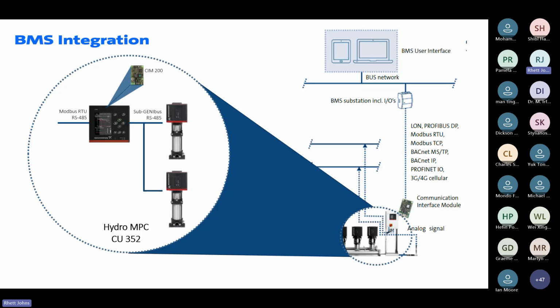Implementing a distributed control strategy in your pump will allow you to have full transparency of the energy consumption and performance of your systems. What I mean by distributed control strategy is that you have localized control within those systems, such as a pump skid, and that pump skid then knows the energy consumption of each individual component within it. So using communication standards such as Profinet, BACnet, etc., and a communication card within these pumps, you can have full data transparency, such as energy, motor speed, pressure set point, and achieved set point, that can be easily communicated back to your SCADA or BMS.